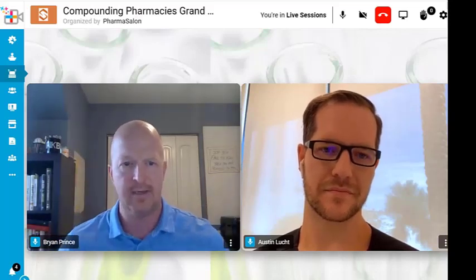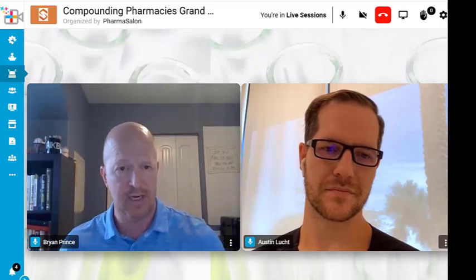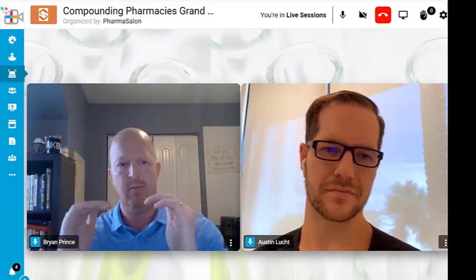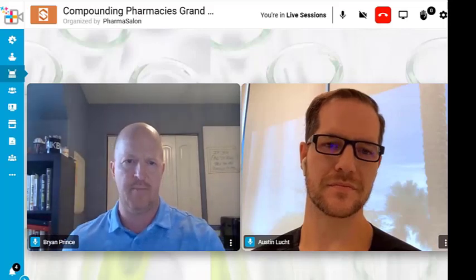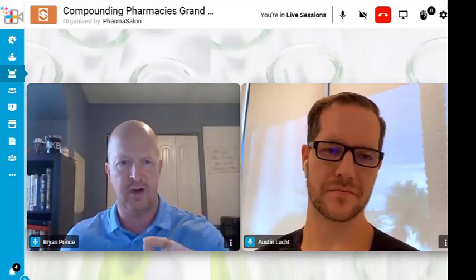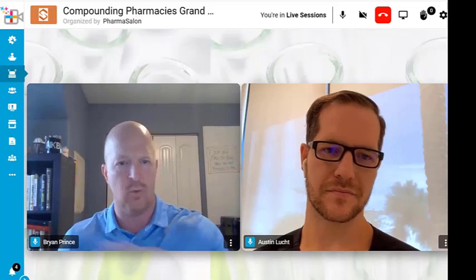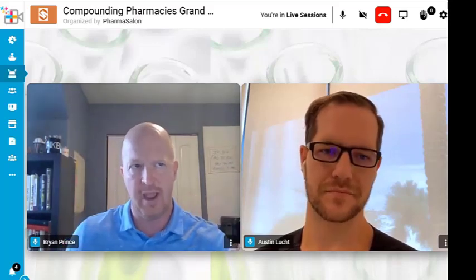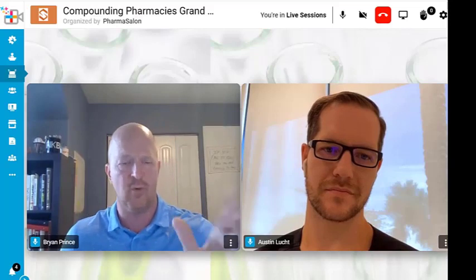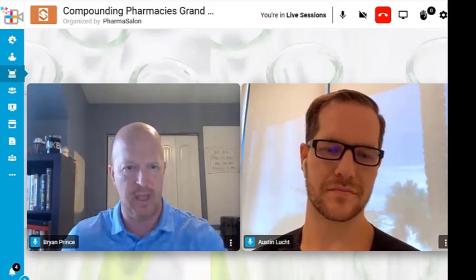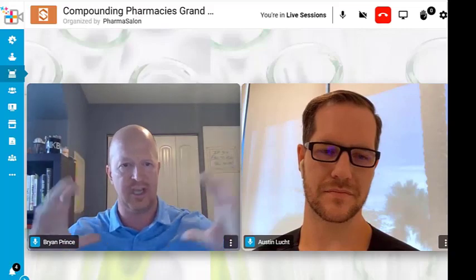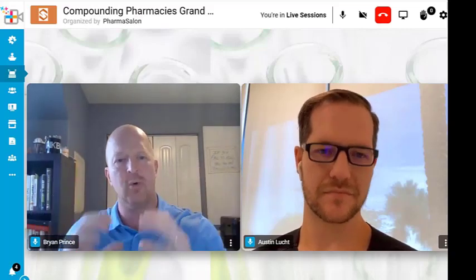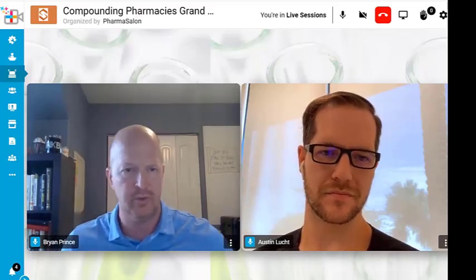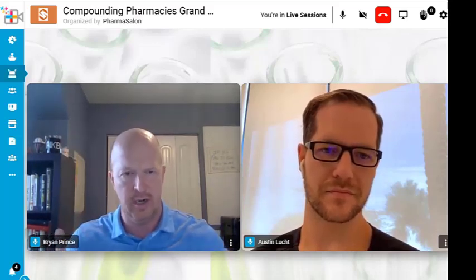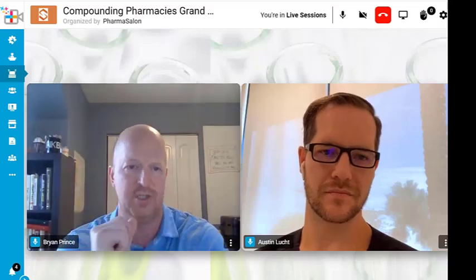So right off the bat, your architect and your engineers, when they spec out the equipment, they need to target that. You never engineer something to the lowest common denominator. So if you engineer it at 68 degrees Fahrenheit and 60% relative humidity, that unit is going to fail. It's got to be 64F. Maybe you would say 63, but let's say 64 degrees Fahrenheit and 50% relative humidity. And yes, that's going to possibly increase the size of the equipment, increase the size of the footprint, increase the number of coils and components inside of that. But you do not want to lose control over your clean room because your engineer didn't know how to spec that piece of equipment. Great question.